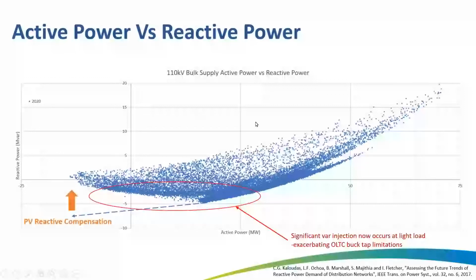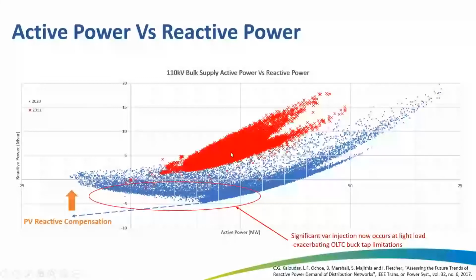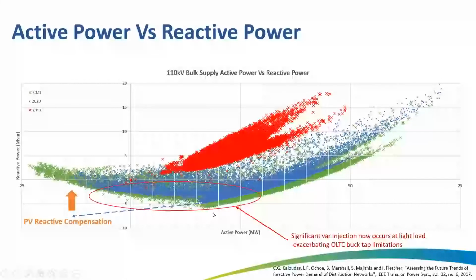In red here now, I've got the same PQ data for 2011, and you can see just how much the load on this has changed. Obviously, this is a new suburb, so we're getting load growth from under 50 megawatts, but we never historically had any capacitive demand, and we of course never had the reverse flows on that network either. So it's quite a significant change there over the last decade. And finally, in green, just quickly, you can see those capacitive flows are continuing to reduce, and those reverse flows are continuing to increase.